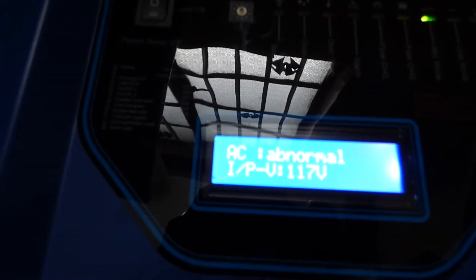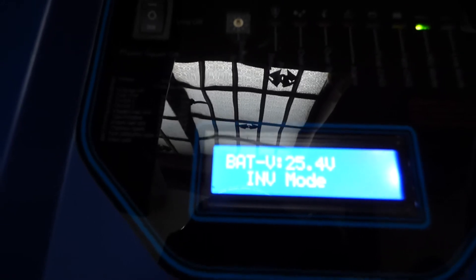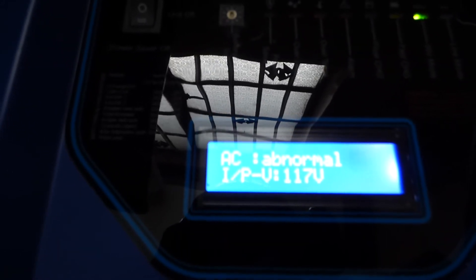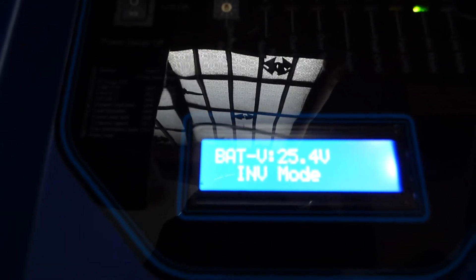As you can see, this updates — give it a second. The display says: abnormal voltage 117 coming from NEPA. Load right now is 19%, we're in inverter mode. You see 117 volts coming from NEPA, 221 is what we're producing, and the batteries are 25.4 volts.